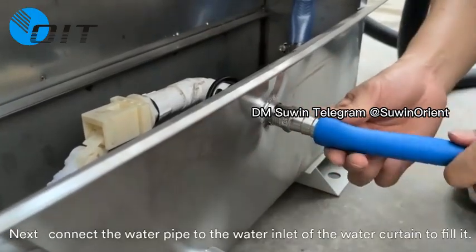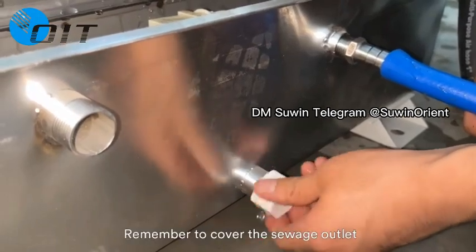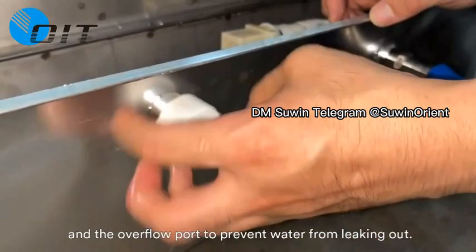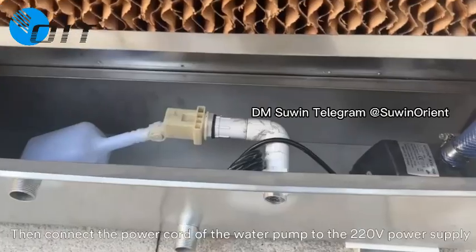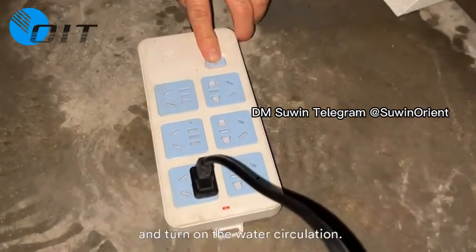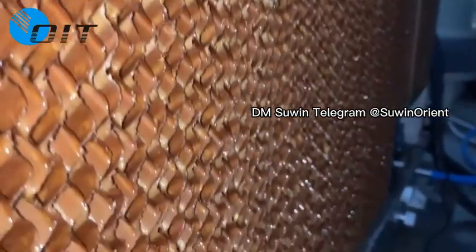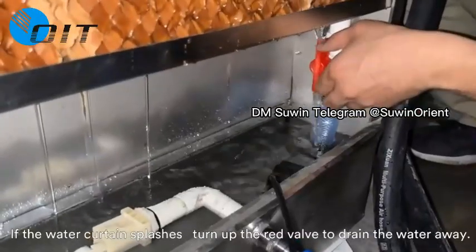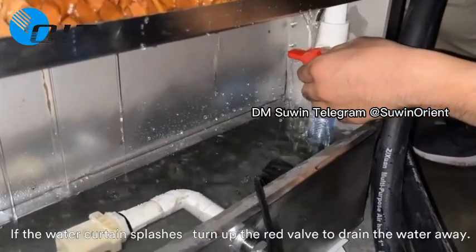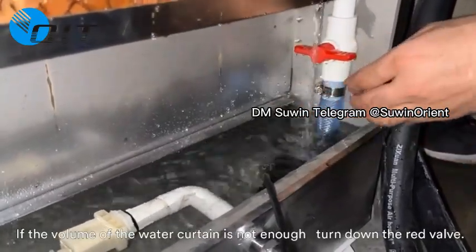Connect the water pipe to the water inlet of the water curtain to fill it. Remember to cover the sewage outlet and overflow port to prevent water from leaking out. Then connect the power cord of the water pump to the 220V supply and turn on the water circulation. We will see the cold water gradually wet the entire water curtain. If the water curtain splashes, turn up the red valve to drain the water away. If the volume of the water curtain is not enough, turn down the red valve.